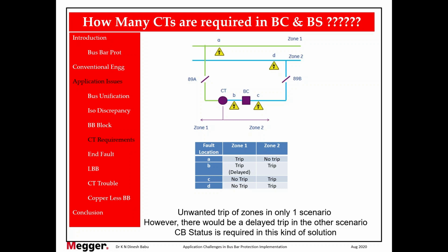Tripping the healthy part is against the protection principle. So it depends, actually. If your substation is connected to a major generation source, you have to go for a dual CT arrangement. No delay is permitted. Delay will reduce the life of other equipment. Whereas if you are in a light load situation, like you are connected to a solar grid, a weak source, it's not going to feed the fault current with very high magnitude for a longer duration. In that scenario, go for this solution. This is cheaper. So it's left to the user. After understanding the pros and cons, they can decide.